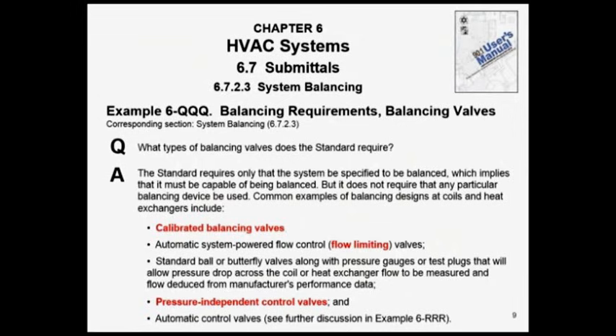The third item, which I did not put in red, is a PT balance, a pressure temperature balance. You can do some balancing with PT, but it's not going to be that accurate, and I just don't think it's going to be satisfactory to you. You can do it. It's a good check on the other three, but you need more than a PT balance. That's just my personal opinion. You can do what you want to, but that's my personal opinion.